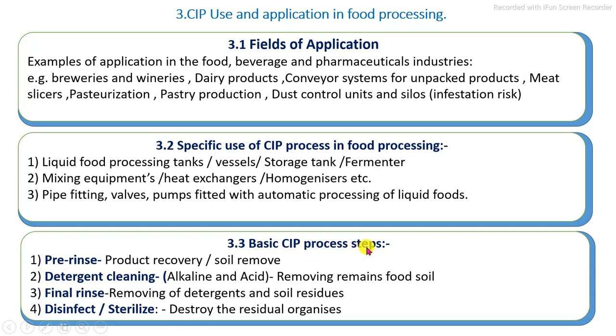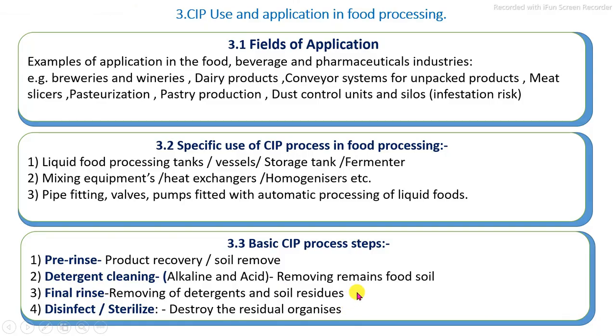The basic CIP process involves four main stages. The first is the pre-rinsing process, in which maximum recovery of food soil is carried out. The second is the detergent cleaning process, using alkaline and acid detergents to remove remaining food soil. The third stage is final rinsing to remove residual detergents and food soils. Finally, a disinfection or sterilization process is carried out to completely reduce the microbial load.